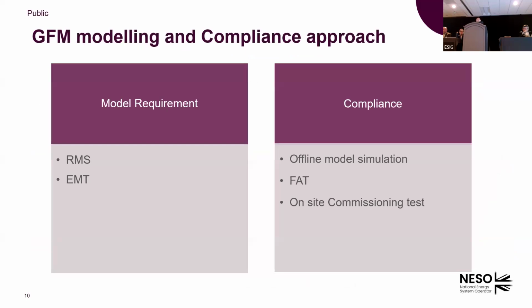I'd like to talk a little bit about the compliance process for this grid forming project. For grid following or any of the existing projects, the compliance process is fairly well established. It goes through different stages: simulation, factory acceptance test, and site testing. For grid forming, it's slightly different, because some of the functionality of grid forming is very difficult to test in a site commissioning test environment, especially if you want to introduce a frequency event, a loss-of-mains ROCOF event, or a phase angle jump event. That is going to be fairly difficult.